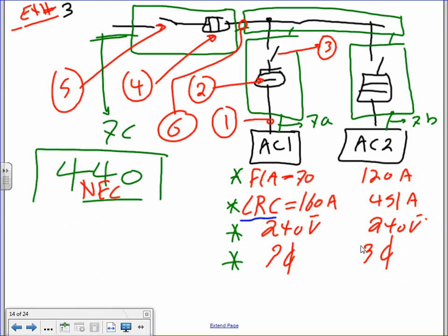Yesterday I walked you guys through two examples of sizing feeders and branch circuits for motors based on Article 430. These two examples I'm going to walk you guys through are also motors, except they're a special type. Article 440 is for HVAC equipment, especially the chillers — anything that has a compressor in it.